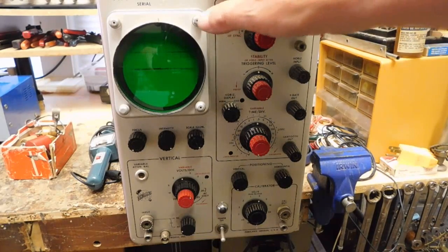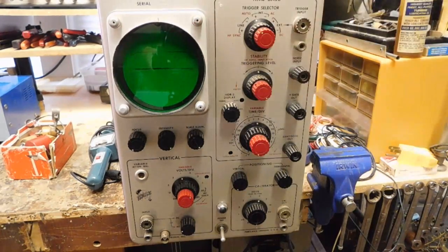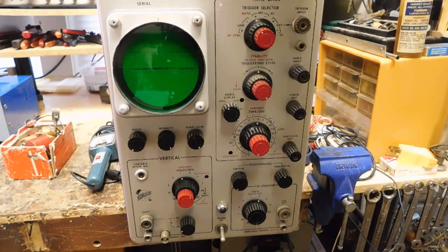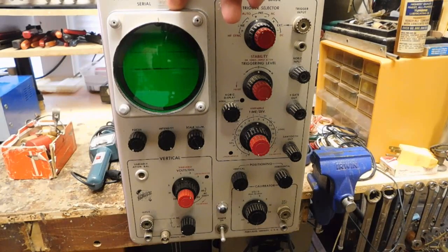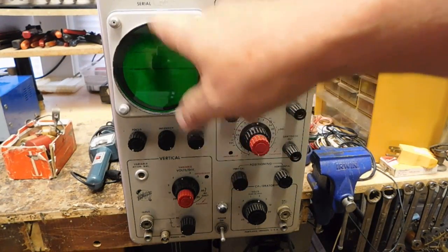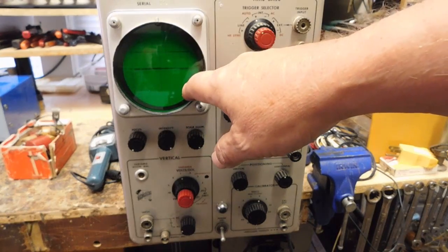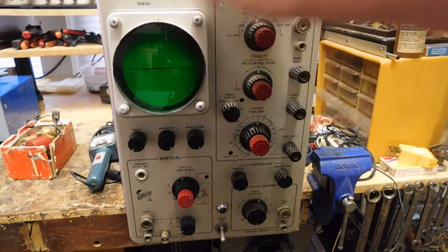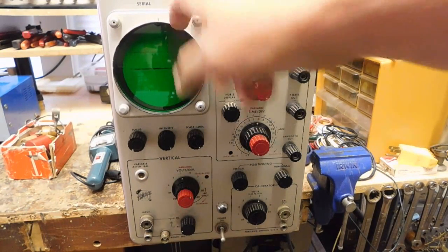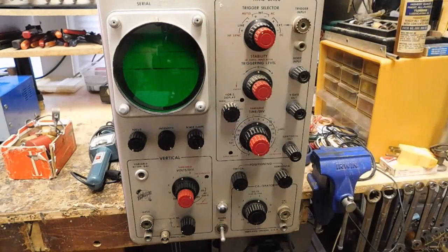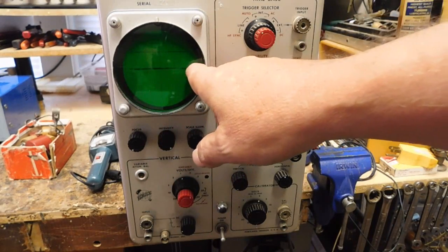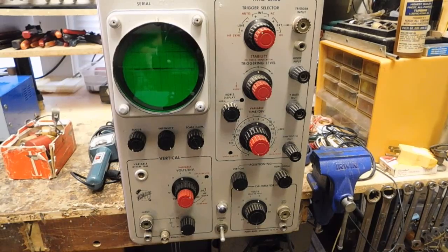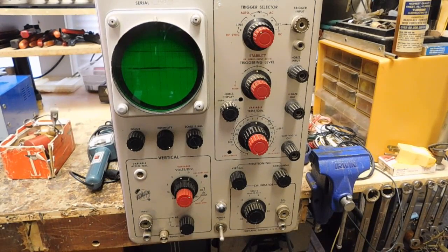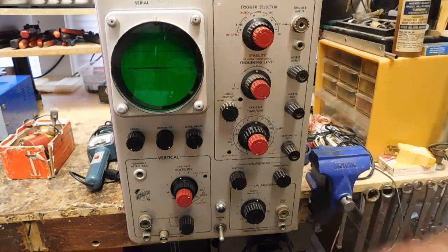But when this was made, it's a sister scope to the 316. The only real major difference between the 316 and 317 is the 316 used a lot lower voltage for the anode voltage, accelerator voltage for the tube. Ran at about 1.5 kilovolts, where the 317 runs at 9 kilovolts. They did that so you didn't need a hood. It was nice and bright. But as you can see, this one has a little problem. It's got burn-in, and although there's actually 2 lines of burn-in, it doesn't seem to be affecting it. Excuse me. You can actually see it real good even when it goes through the burn-in. It still produces some light.